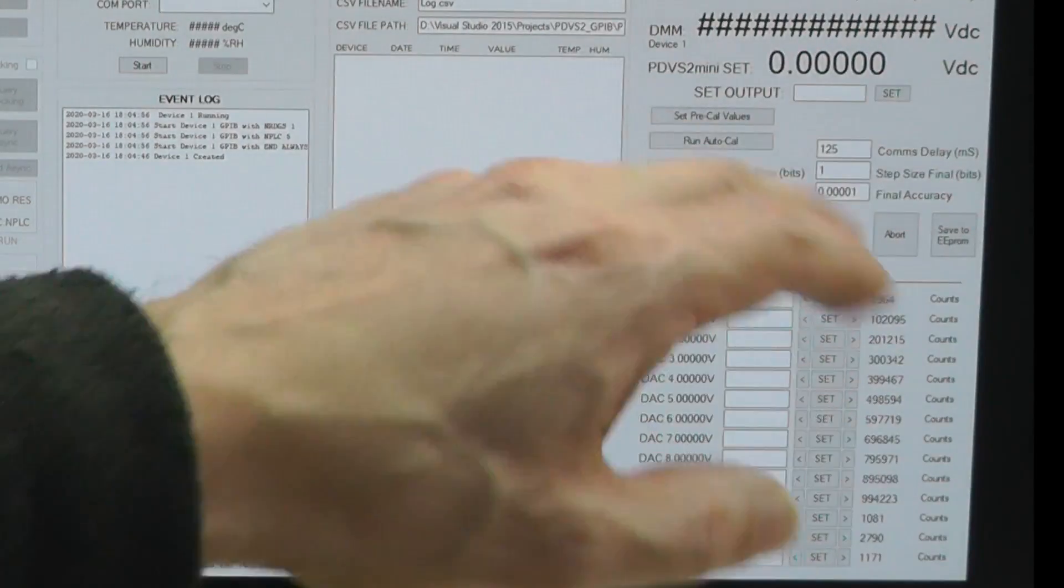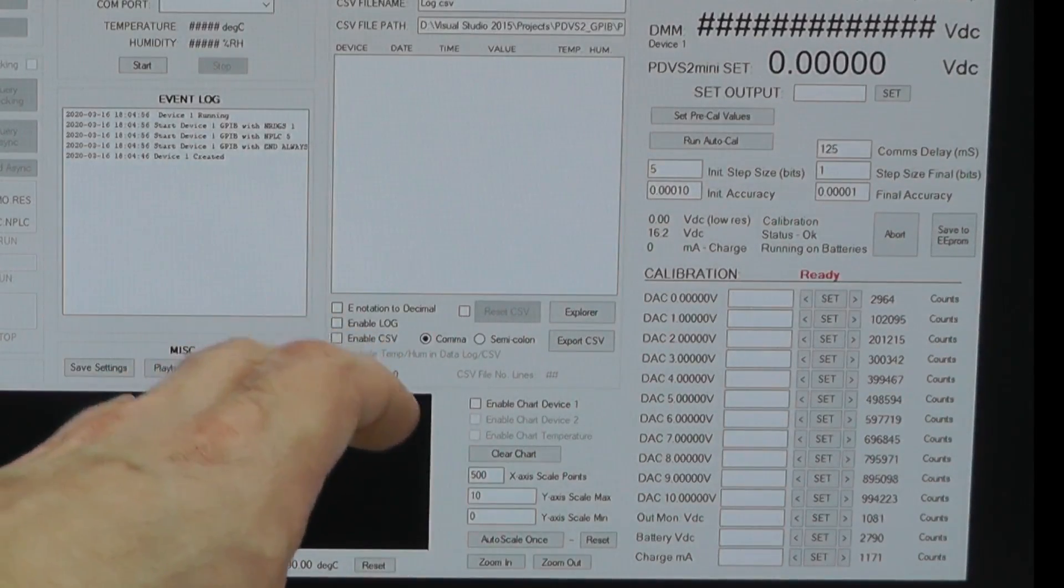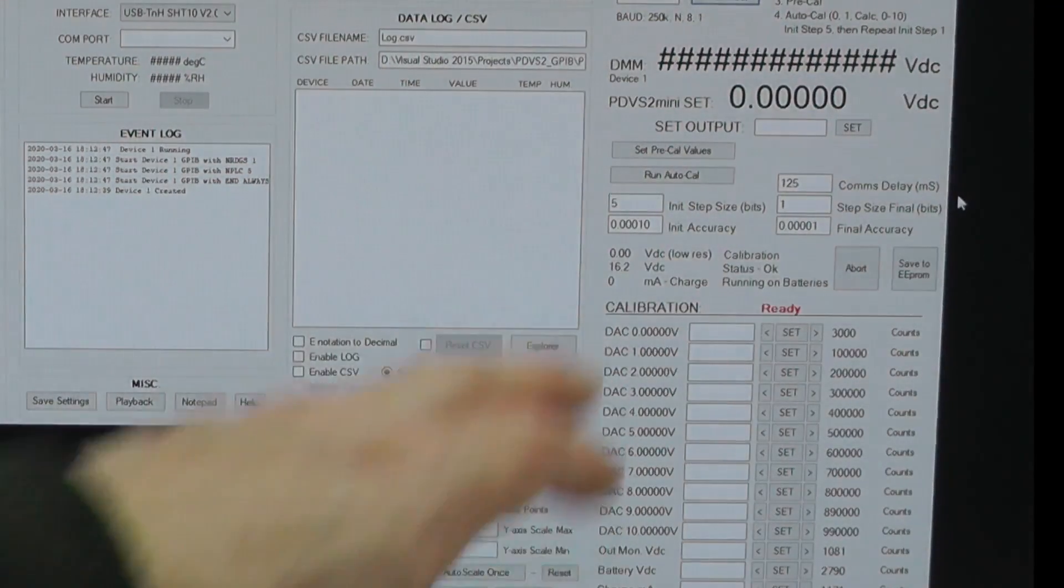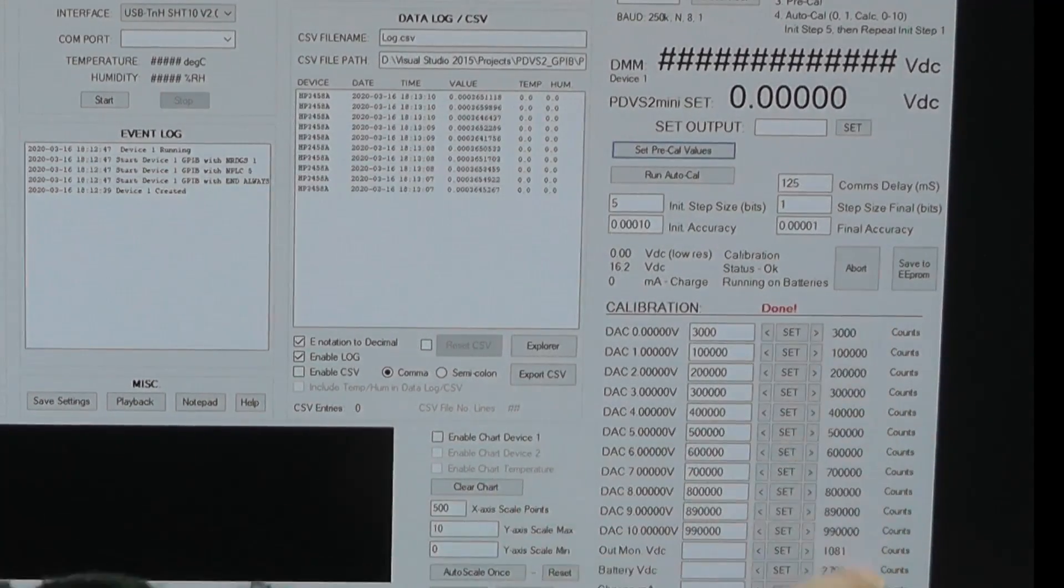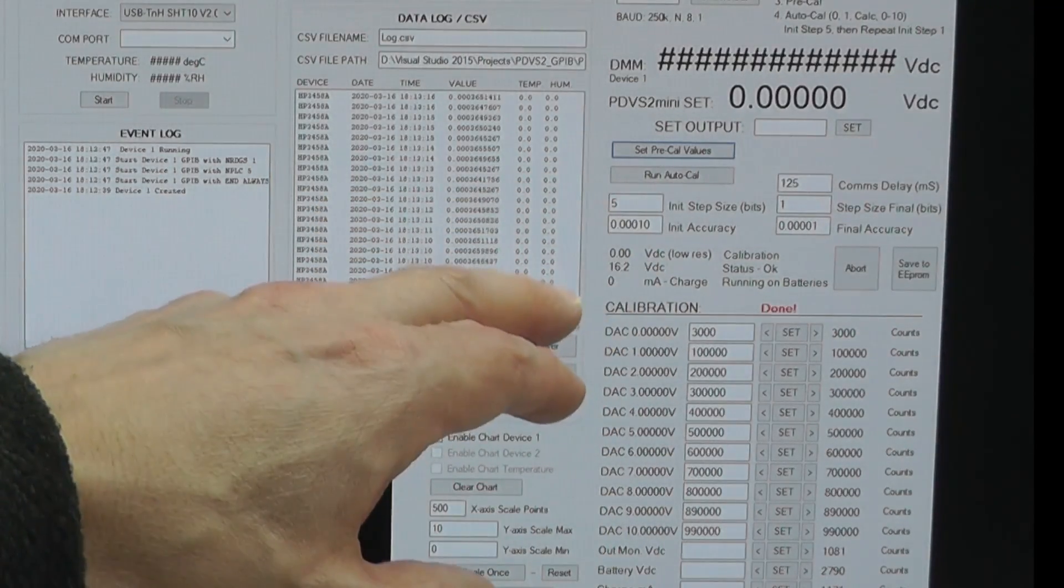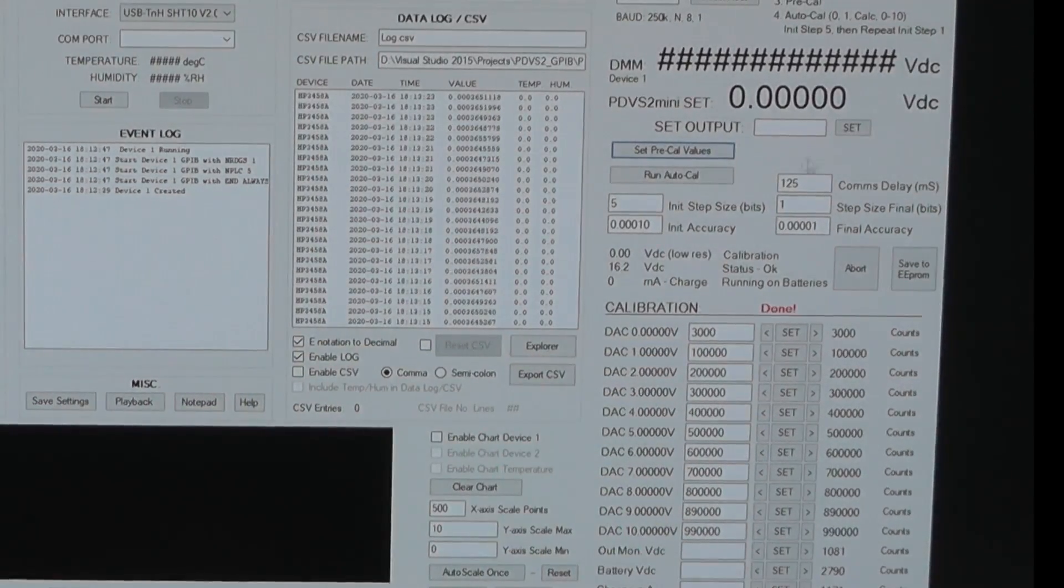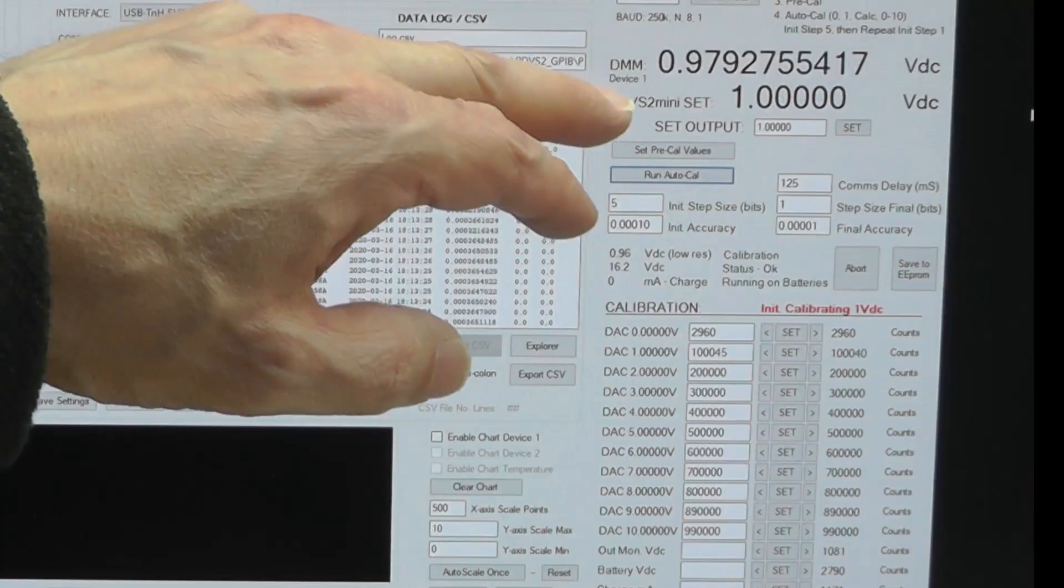Sound a little bit complicated so hope you're still with me but what I'm going to do now is I'm going to run the program here. I'm going to set the pre-cal values and then once that's done I'll run the auto cal and you'll see it running. You won't really see much on the left hand side, you'll see the log window data start to appear there because that's just the communication and the readings that it's getting back from the 3458A. We're really just running this section here. So the first thing I'll do is send the pre-cal values to the PDV-S2 Mini by hitting that button there and there it is, it's sending all that data and that's it done. So there's the values in the PDV-S2 Mini - that's the ones that were sent. Now I can run the auto cal and it'll start doing the first pass which is work out the calibration for the first two set points and then it'll guess the rest or calculate the rest. So there we go, initial calibrating zero volts - you can see it counting down to zero, it's done that, it's away off to do one volt now.